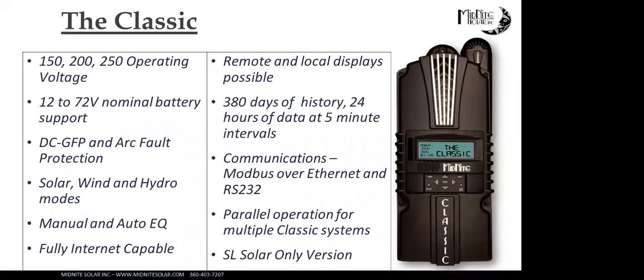You can set skip days for 5, 7, 15, whatever number the battery manufacturer likes. And what it'll do is every morning it'll wake up and do a float charge until it hits that number of days. So if you set it for 15, it'll wake up and float 15 days in a row, 14, and on the 15th day it will do a full bulk and an absorb charge, and then go to float.